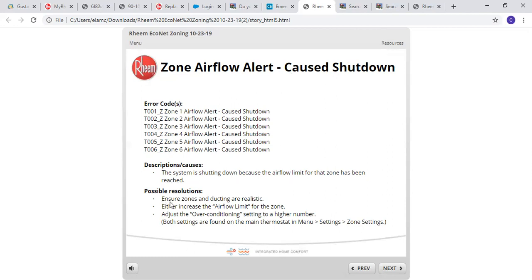So possible resolutions: ensure zones and ducting are realistic. Either increase the airflow limit for the zone, or adjust the overconditioning setting to a higher number. Both settings are found in the main thermostat, in the menu settings and zone settings. So you have to make sure, one, that your duct can truly handle that. A lot of times you'll catch some of this before you get to this point, usually in the setup. But it's telling you that you've reached the airflow limit for that zone. So you need to relieve some pressure. You need more duct. More duct or less airflow.